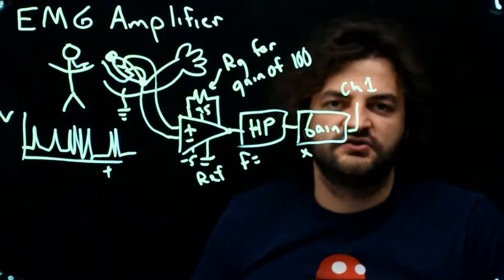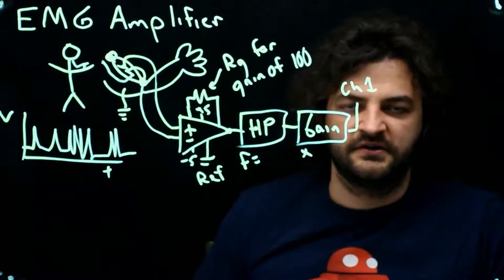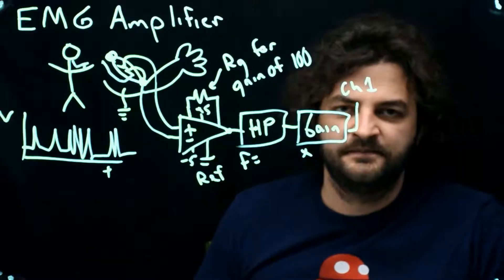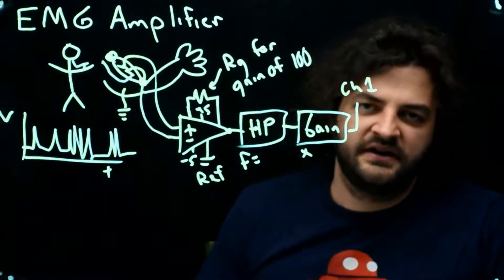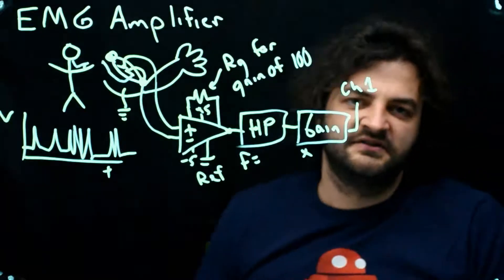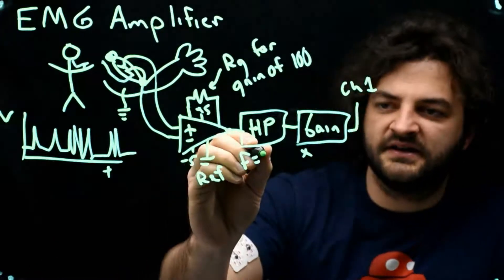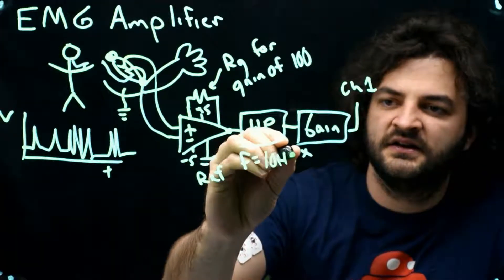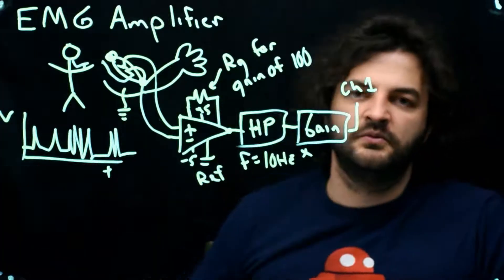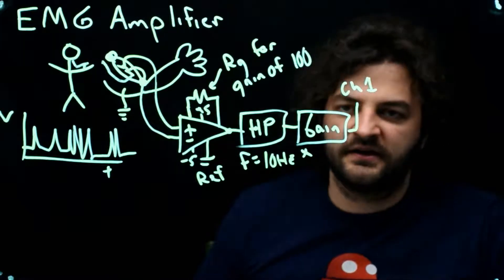How do you choose a high-pass filter frequency and how do you choose the gain? We're definitely trying to get rid of 1 hertz components from my heartbeat from ECG. So we want the high-pass to be above 1 hertz. If you've ever looked at this kind of stuff in another biomedical engineering class before, you'd see that the EMG signal is something in the hundreds of hertz. So let's choose our high-pass to be around 10 hertz. Then we can adjust later on.